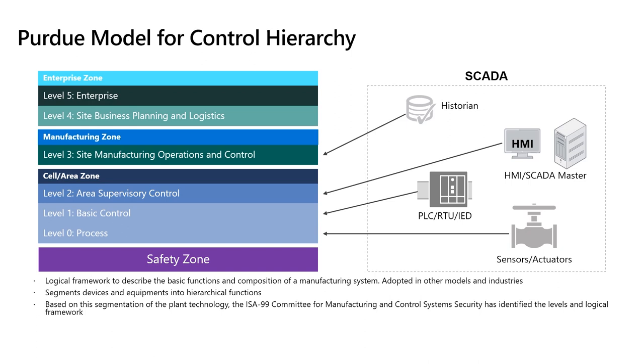Below all levels of the Purdue model is the safety zone, which bleeds through all levels. Level zero is the electrical layer — where electrical motors and actuators live, the physical process itself. Level one is where electrical starts meeting basic controls: is a switch on or off, or switching on and off so fast it creates half-speed motor control — pulse width modulation, or PWM.